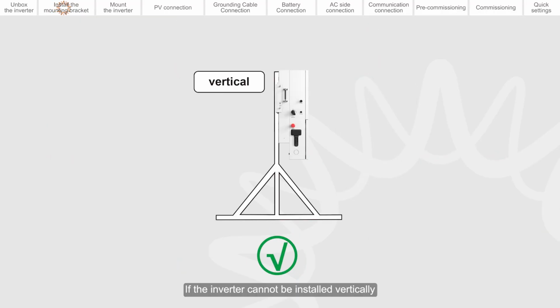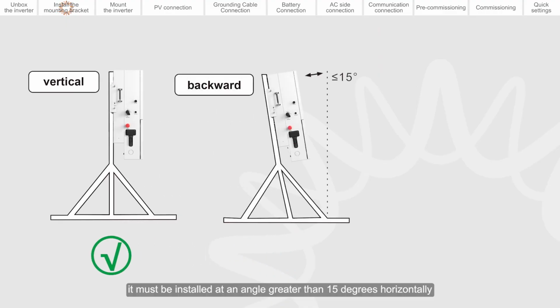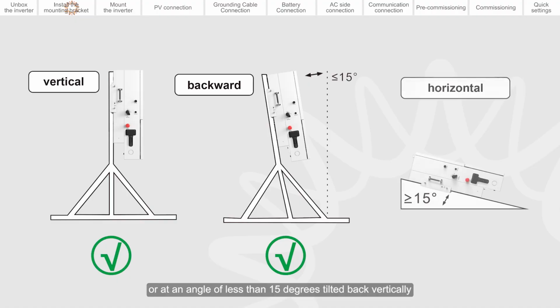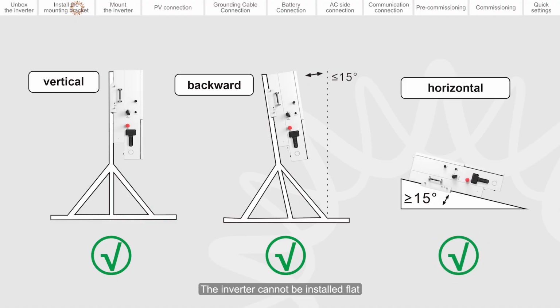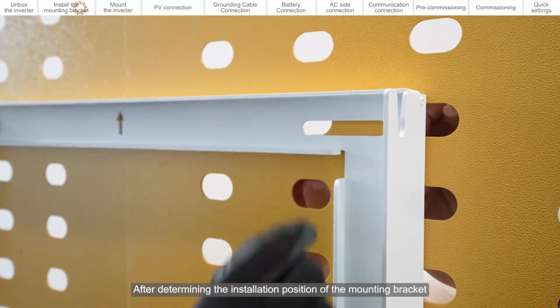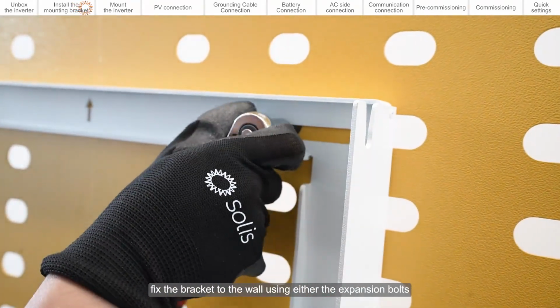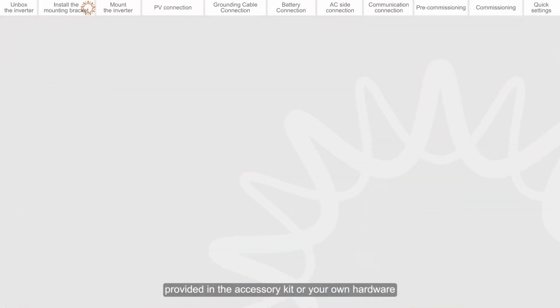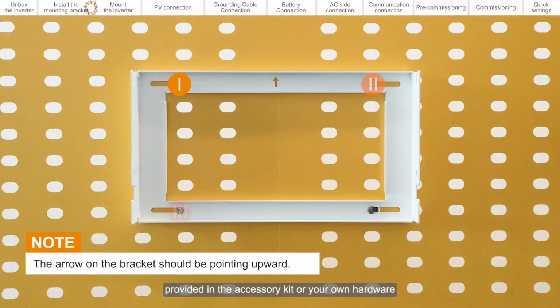If the inverter cannot be installed vertically, it must be installed at an angle greater than 15 degrees horizontally, or at an angle of less than 15 degrees tilted back vertically. The inverter cannot be installed flat. After determining the installation position of the mounting bracket, fix the bracket to the wall using either the expansion bolts provided in the accessory kit or your own hardware.